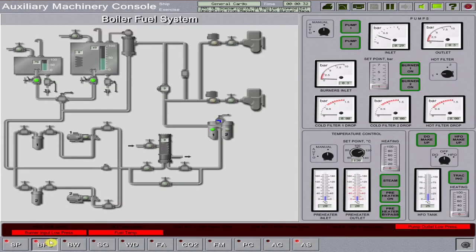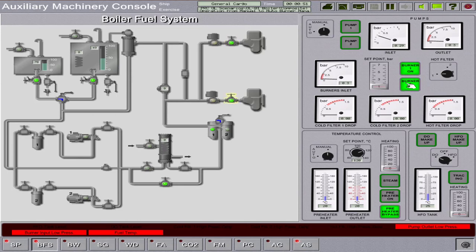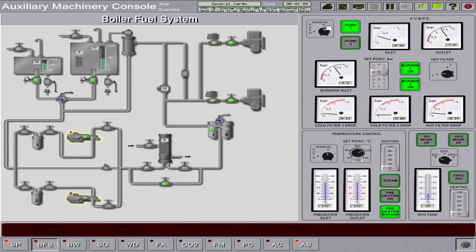Proceed to the boiler fuel system and line up the system for diesel oil circulating to the burner. Open your preheater bypass selector switch and set to the oil open position. Open burner stop valves one and two. Adjust the boiler fuel pump set point to five bars, then start one fuel pump and set it to auto running condition.